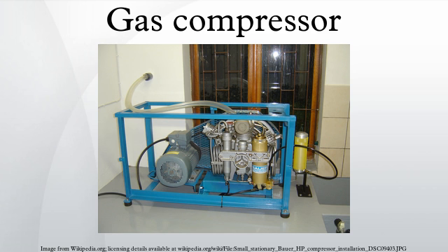The difference between the hermetic and semi-hermetic is that the hermetic uses a one-piece welded steel casing that cannot be opened for repair. If the hermetic fails, it is simply replaced with an entire new unit. A semi-hermetic uses a large cast metal shell with gasketed covers that can be opened to replace motor and pump components. The primary advantage of a hermetic and semi-hermetic is that there is no route for the gas to leak out of the system. Open compressors rely on either natural leather or synthetic rubber seals to retain the internal pressure, and these seals require a lubricant such as oil to retain their sealing properties.